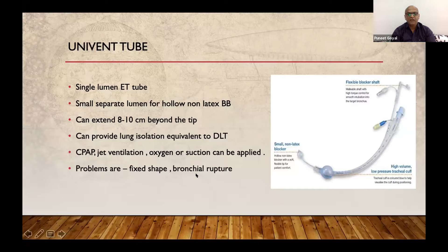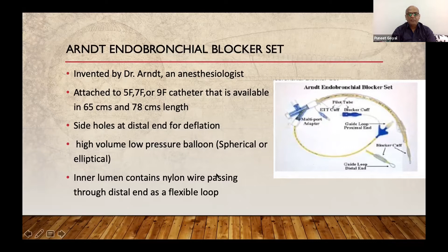Then second is the most common bronchial blocker, the Arndt bronchial blocker. It was invented by Dr. Arndt, who himself is an anesthesiologist, and they are available in 3 sizes, 5, 7, and 9 French, and 2 lengths, 65 and 78 centimeters. There are side holes at the distal end for deflation, and they have a high volume, low pressure balloon, which is spherical or elliptical in shape. And then the inner lumen contains a nylon wire, which can be passed through the bronchoscope.